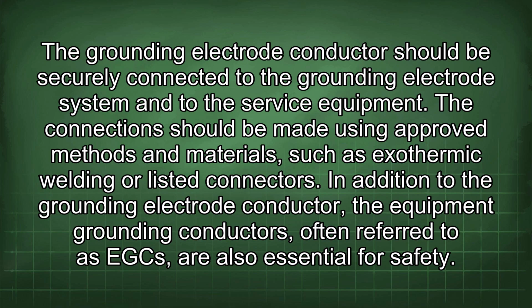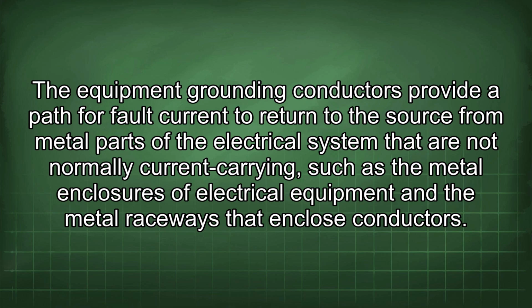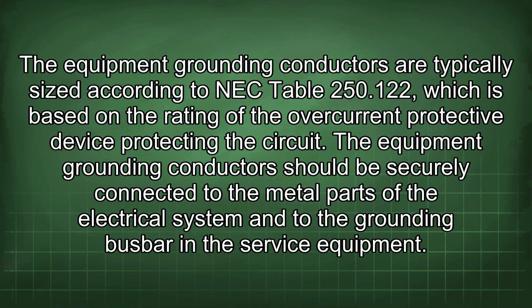In addition to the grounding electrode conductor, the equipment grounding conductors, often referred to as EGC, are also essential for safety. The equipment grounding conductors provide a path for fault current to return to the source from metal parts of the electrical system that are not normally current carrying, such as the metal enclosures of electrical equipment and the metal raceways that enclose conductors. The equipment grounding conductors are typically sized according to NEC Table 250.122, which is based on the rating of the overcurrent protective device protecting the circuit.